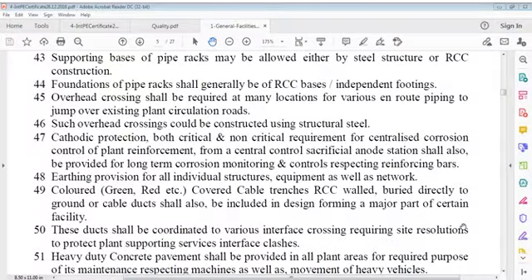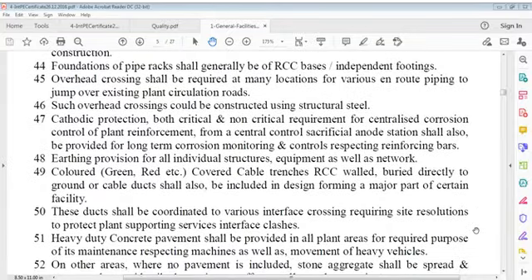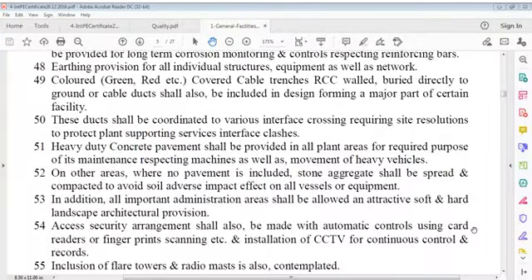Cathodic protection, both critical and non-critical requirements for centralized corrosion control of plant reinforcement from a central control. A sacrificial anode station shall also be provided for long-term corrosion monitoring and controls respecting reinforcing bars. Earthing provisions for all individual structures, equipment as well as network. Colored, that is green or red, etc. Covered cable trenches, RCC walled, buried directly to ground or cable ducts shall also be included in design, forming a major part of certain facility.